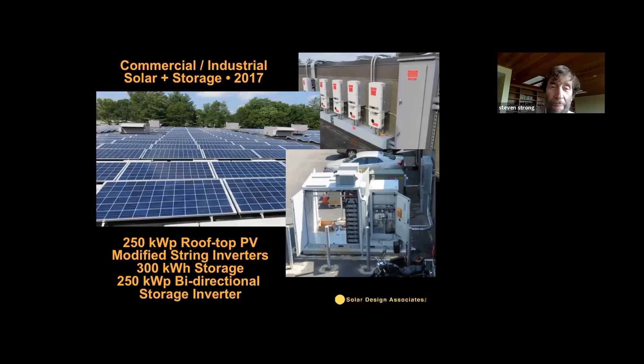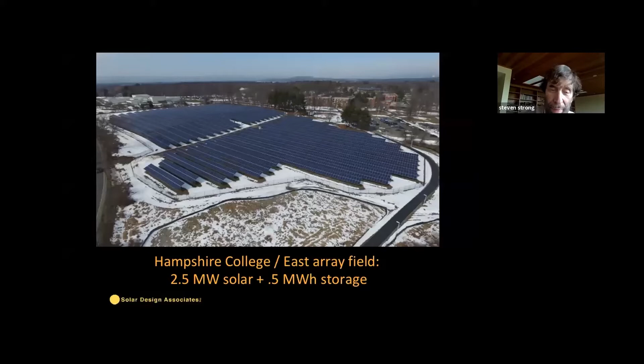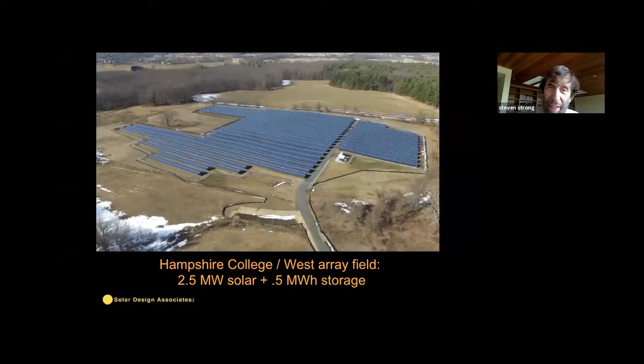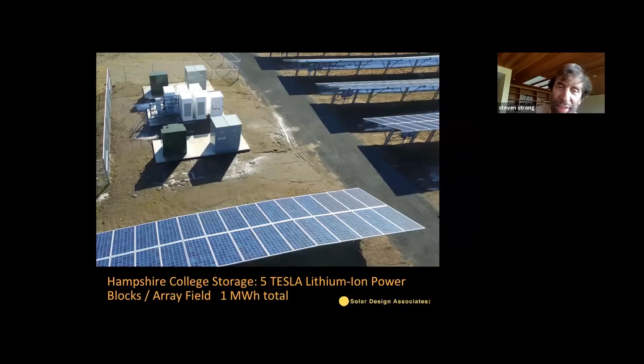We helped Hampshire College, in Western Massachusetts, power their entire campus with solar plus storage. There's 5 megawatts of solar in 2 separate array fields, each with 0.5 megawatt of storage, for a total of 5 megawatts of solar and a megawatt hour of storage. There's a cluster of 5 Tesla power blocks, each with 100 kilowatt hours, for half a megawatt. You see the power electronics and the transformers as well.